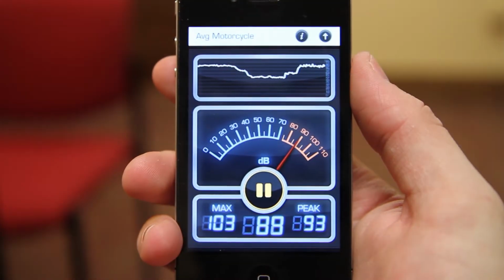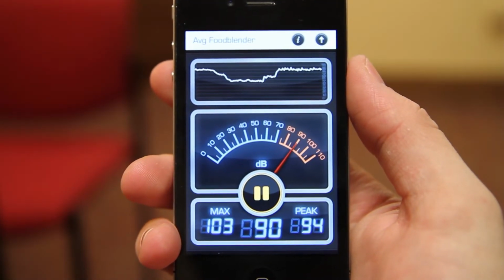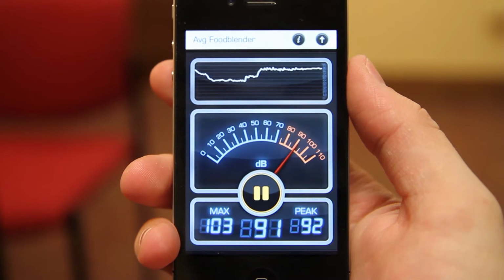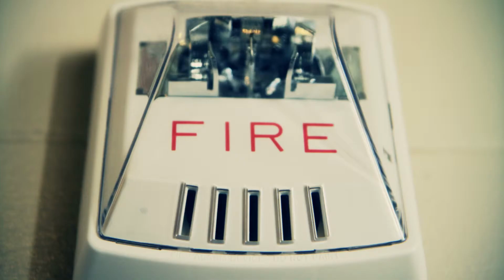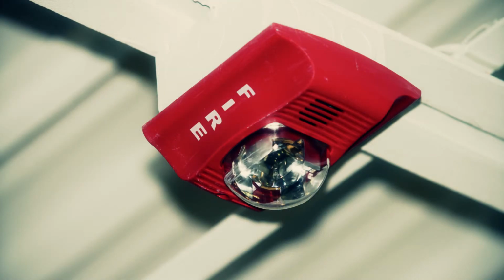Those alarm devices have to ring at a minimum of 85 decibels, so 85 to 110 is what they're typically set at. When you walk out into a corridor of a large office building, you should see audio-visual devices in the corridors, either on the walls or mounted to the ceiling. And they should have noise and a lot of light. It's to alert you, to help you get out and remind you, hey, it's time to go.